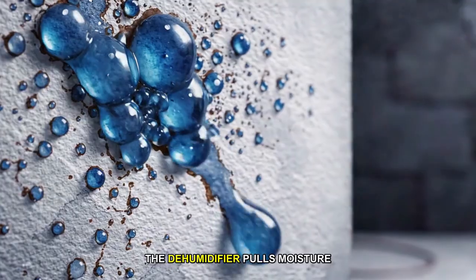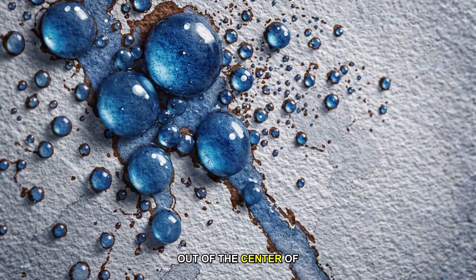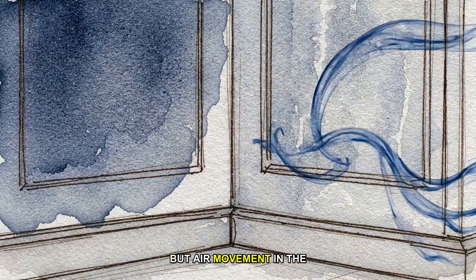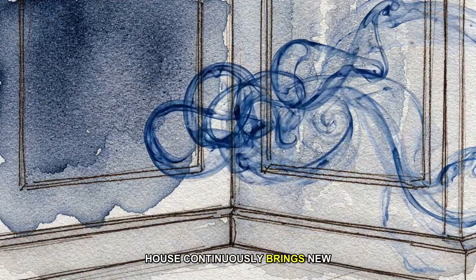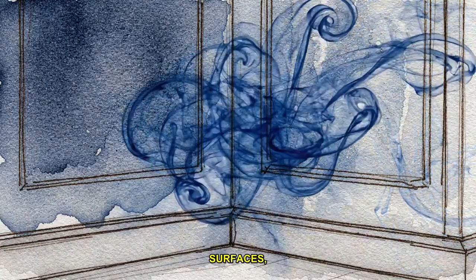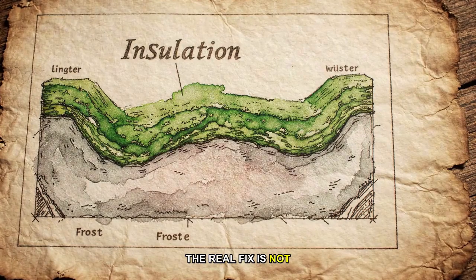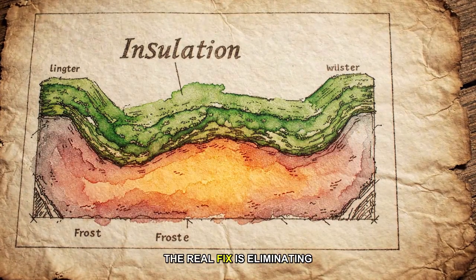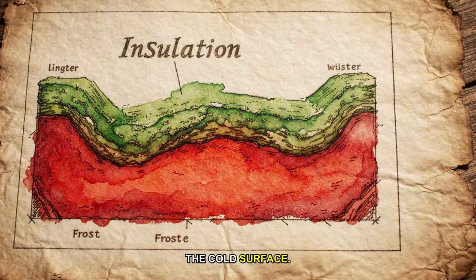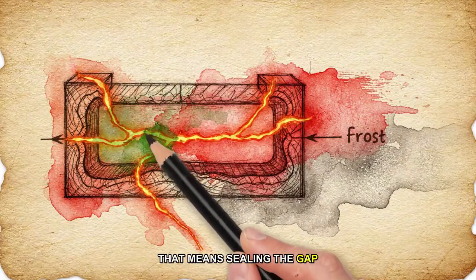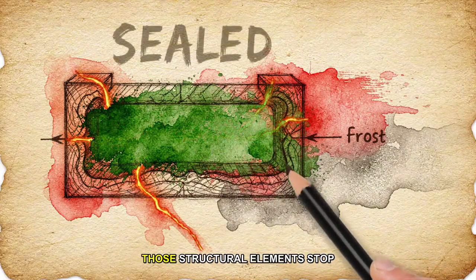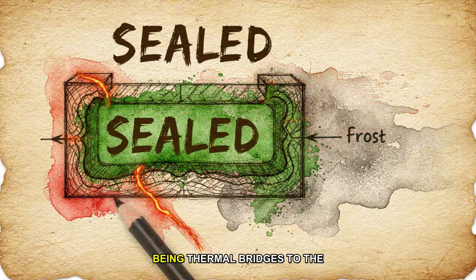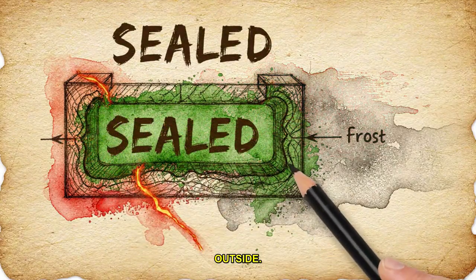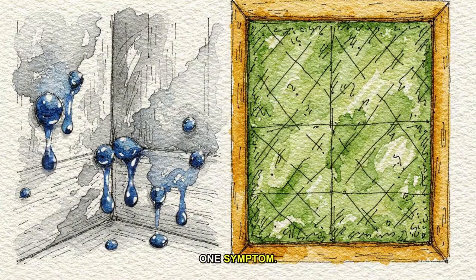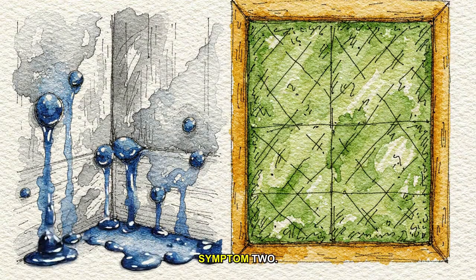The dehumidifier pulls moisture out of the center of the room. But air movement in the house continuously brings new humid air to those cold surfaces, and the process repeats. The real fix is not drying the air. The real fix is eliminating the cold surface. That means sealing the gap in the thermal envelope so those structural elements stop being thermal bridges to the outside. One symptom. One root. Symptom 2.